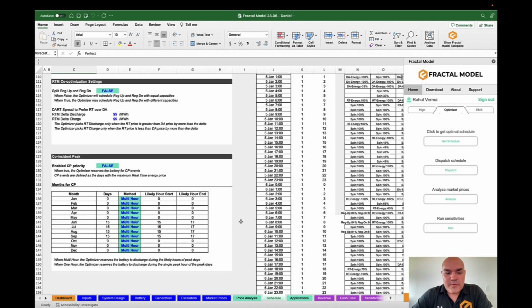The last thing to show you, we can incorporate peak mitigation with optimizing revenue. And the way we set it up, you can tell the model, I'd like to reserve however many days per month to mitigate peaks. Right now we have a pretty big number. Maybe this is too big. Just for instance, we could come in here and we could say 15 days of the year, I think I'm going to need to shift energy using my battery so that I'm sure that we will offset that peak.